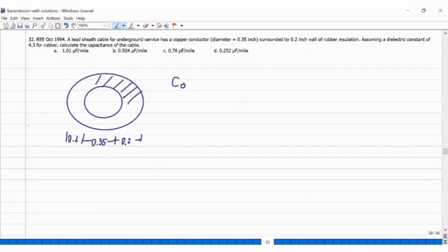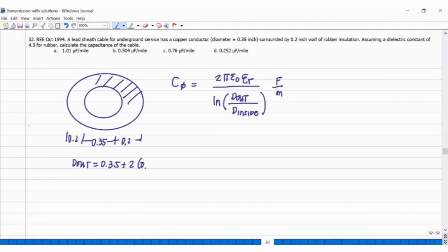Yung capacitance ng cable per phase, so 2 pi epsilon naught epsilon r. Pag cable na ganyan na may insulation, you can have the radius or you can have the diameter. The outside diameter, mas malaki kasi yan, divided by D inside. This is in farad per meter. Madalas din, microfarad per mile. So, mag-convert tayo. Ano yung D out? 0.35 plus 2 times the insulation, 0.2. So, 0.75 inch. Yung inside diameter is yung diameter ng conductor, 0.35 inch.